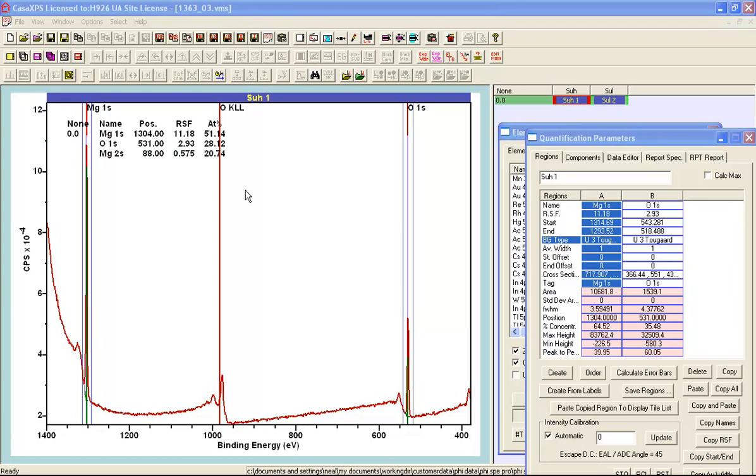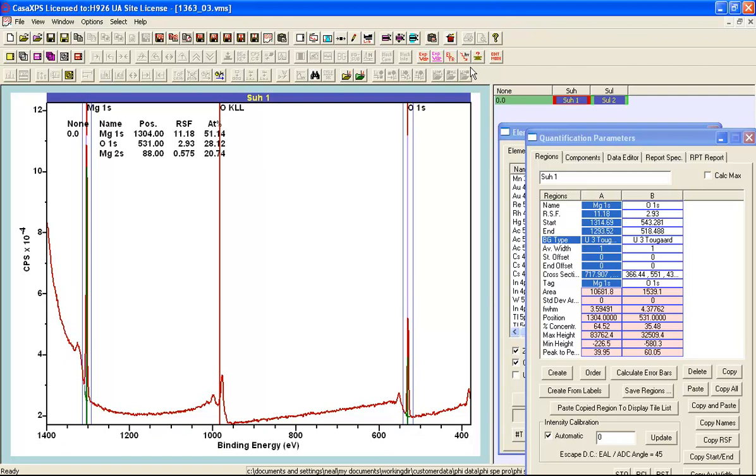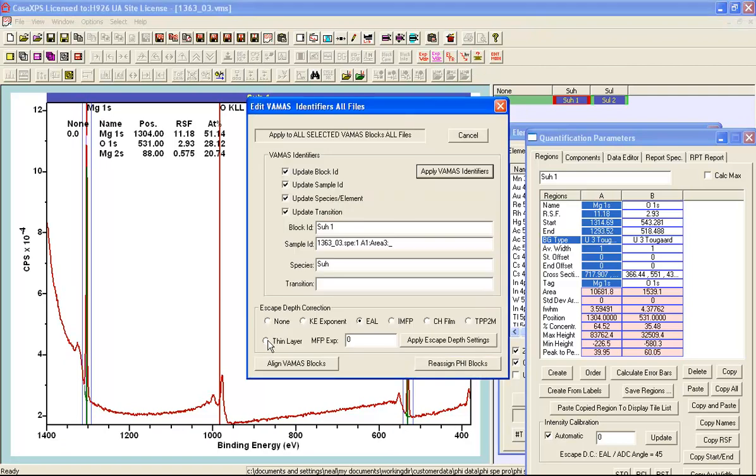The problem with this quantification could be related to the fact that I have used an effective attenuation length to correct for the escape depth. Now this makes an assumption that we have a bulk material. But if this is a thin film at the surface then correcting as if it is a bulk will give us an incorrect quantification. Now there is an option that allows a thin film of a material to be quantified. What I have to do is specify that I need a thin film correction as opposed to the effective attenuation correction. And enter a value that is a measure of how thick I believe the film should be. So I am going to enter 3 and I press apply escape depth settings.